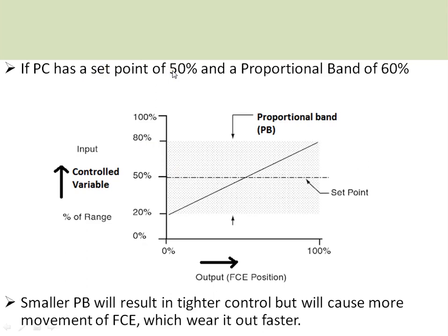This can be understood from this figure. If a proportional controller has a set point of 50 percent and a proportional band of 60 percent, the band spans plus or minus 30 percent around the set point — giving a range from 20 to 80 percent. For example, if the process range is 0 to 100 degrees, the set point is 50 degrees and the proportional band covers 20 to 80 degrees, representing an error range of 30 degrees on either side — covering 0 to 100 percent of the controller output.